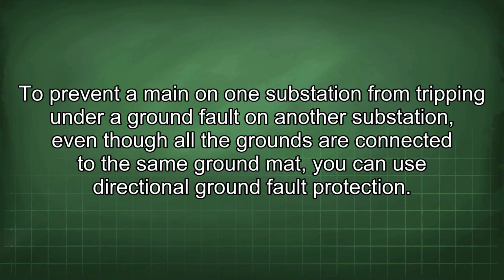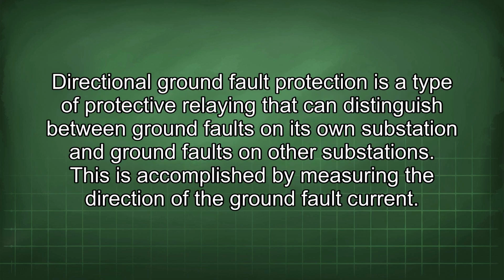To prevent a main on one substation from tripping under a ground fault on another substation, even though all the grounds are connected to the same ground mat, you can use directional ground fault protection. Directional ground fault protection is a type of protective relaying that can distinguish between ground faults on its own substation and ground faults on other substations. This is accomplished by measuring the direction of the ground fault current.